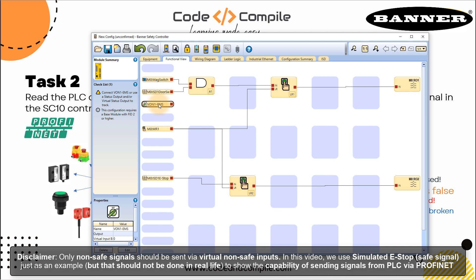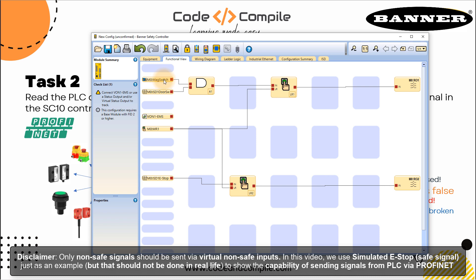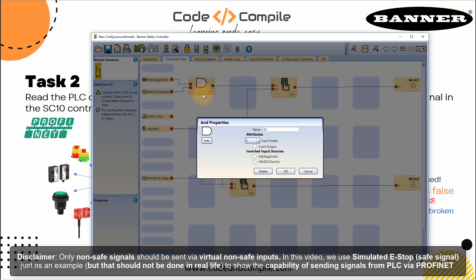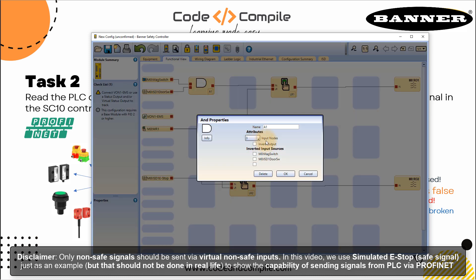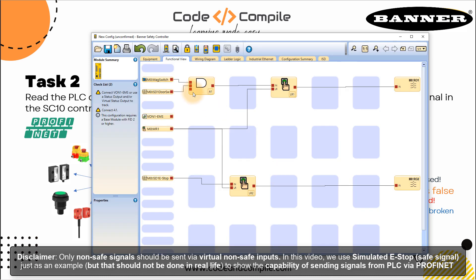Now you can see that this input is here. All I have to do is connect this input in series with these two LR blocks. For example, I have a magnetic switch, a door switch — I can connect e-stop as well. Or I can also connect e-stop to the output, depending on how I want to associate my outputs. Let's say I want to connect this in both circuits — R01 and R02. In this case, I will open this block, make three inputs, and click okay. Now I have an extra input and I can connect this here.